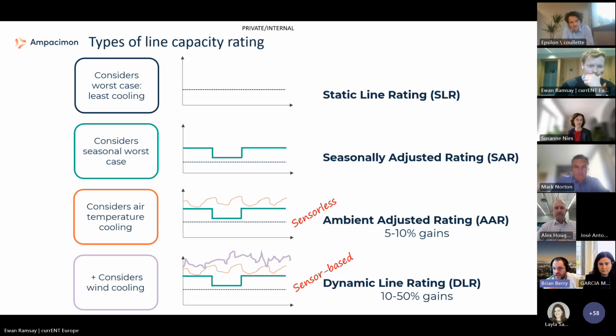I don't need sensors on the line. I can go pure software, get weather provider data and get it into the system very quickly. On the dynamic line rating side, you need sensors to get an understanding of the wind. Wind is a bit more unpredictable and harder to get a handle on. But once you get that wind component, you can get values up to 50% extra capacity, sometimes even more. Really, we've seen some cases of even an extra 100% capacity gain at certain times.